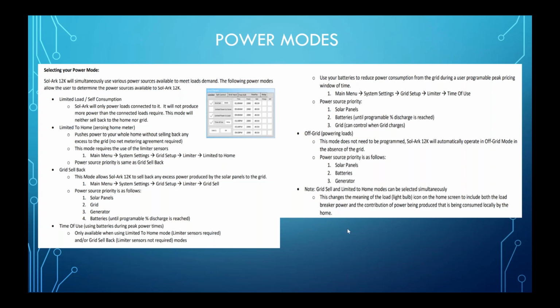The next one is going to be Limited Power to Load. Limited Power to Load is directly just whatever's connected to the load breaker of the system. This will be mainly for your off-grid. So if you are off-grid, this is the mode you would select, obviously, because we don't have a main service panel or a utility to sell back to.